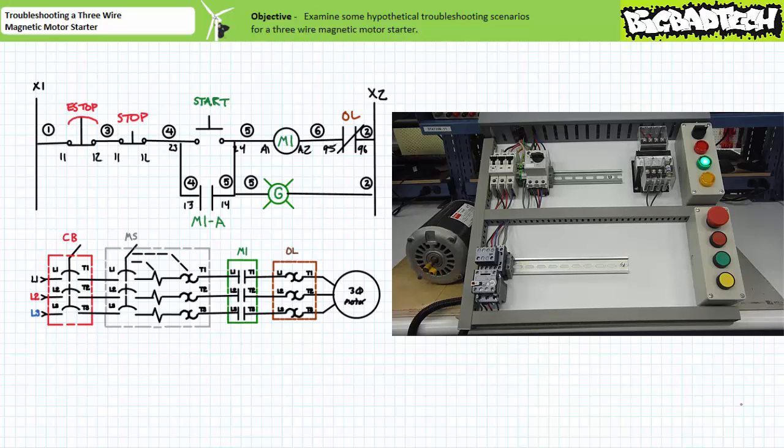Note, however, the pilot-level ladder logic provided by the still-energized control transformer downstream of the closed circuit breaker and upstream of the open manual motor starter remains energized. The contactor coil remains energized and the contacts remain closed. If these clues are subtle enough to escape your attention, note the pilot light remains illuminated indicating the pilot-level ladder logic is maintaining the holding circuit. The moment the manual motor starter is closed, the motor springs to life. Let this be a lesson you hopefully never have to learn again.